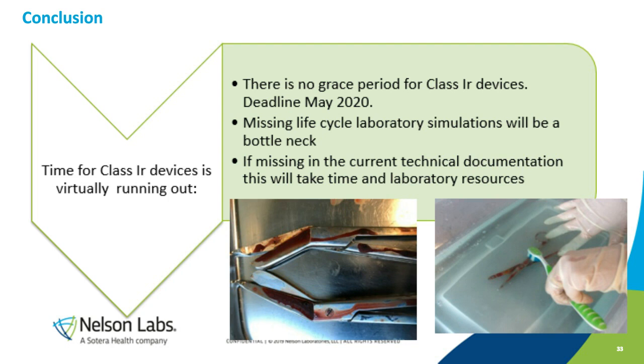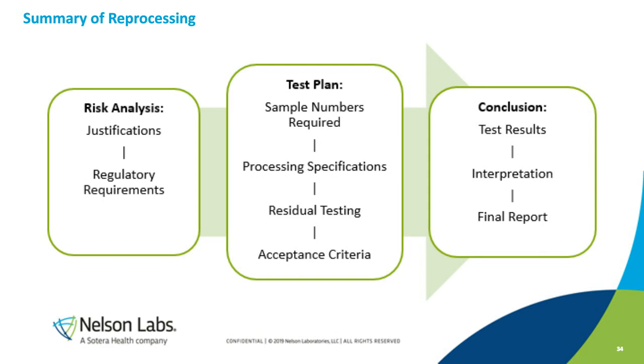I just want to go over the summary of reprocessing, and we want to show that, first of all, we need to perform a full risk analysis that includes all justifications and how we are going to meet all regulatory requirements. And then we write the whole test plan, which includes the sample numbers that will be validated, all processing specifications, all residual testing that will be performed, and the acceptance criteria that will need to be met. After the testing is performed, then a conclusion is written, which includes all the results for the testing, interpretation of those results, and the final reports of all the testing.